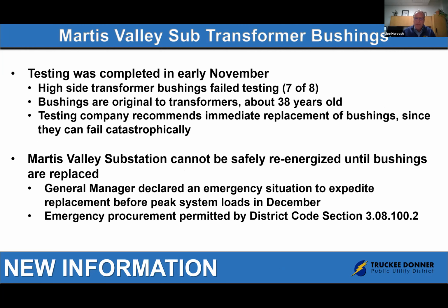Now, these bushings are original to the transformers, meaning they're about 38 years old. The other important fact is that they are also of a manufacturer model and type that is subject historically to very high failure rates within the industry. This is not a good unit.